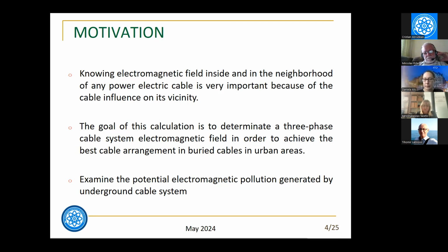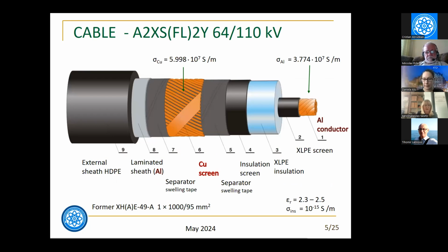Those single cables do not have any ferromagnetic element, and in each of them there is one phase of the three-phase power system. For the harmless application of electrical energy, the electric and magnetic field values are limited by international and domestic standards, and all the fields produced by high voltage buried cables must be less than the maximal allowed values. For this reason, all calculated or measured electromagnetic field values are always compared with the values defined in standards. The high voltage power cable in our calculations is this one in the picture.